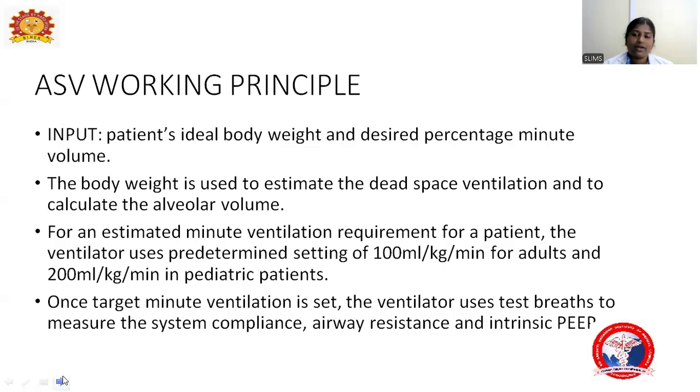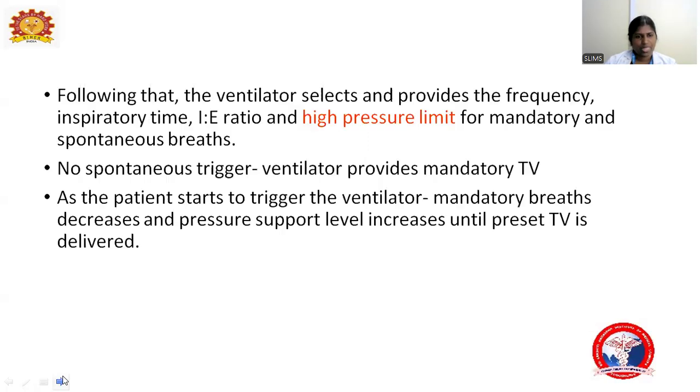Once target minute ventilation is set, the ventilator uses test breaths to measure the system compliance, airway resistance, and intrinsic PEEP. Following that, the ventilator selects and provides the frequency, inspiratory time, that is I:E ratio, and the high pressure limit for the mandatory and spontaneous trigger. If there is no spontaneous trigger, the ventilator will provide the set mandatory tidal volume.